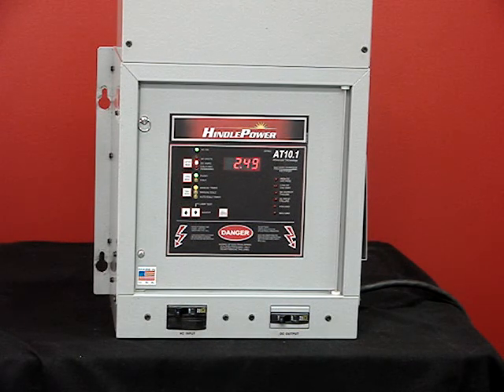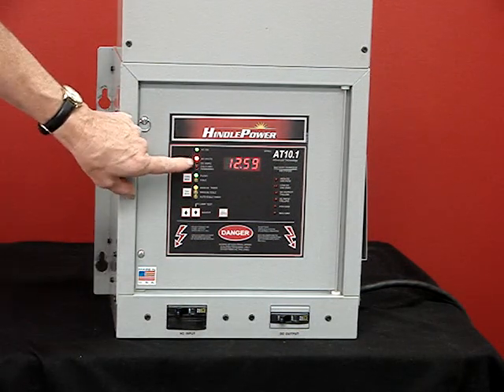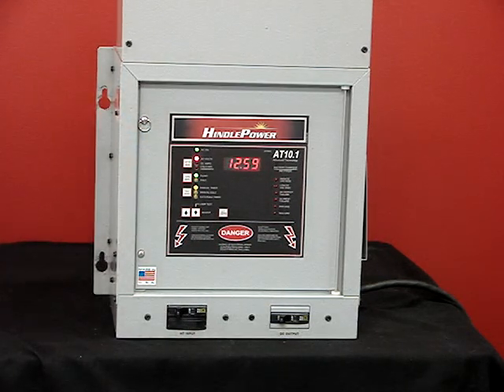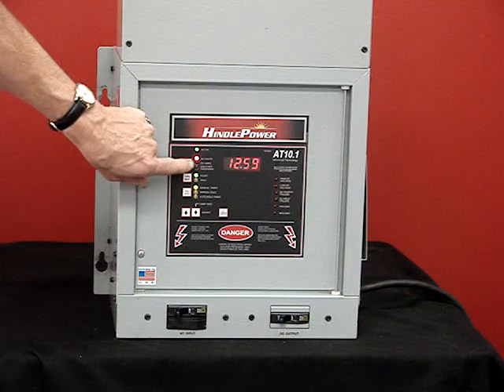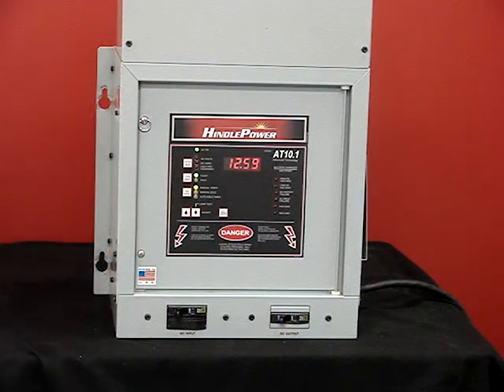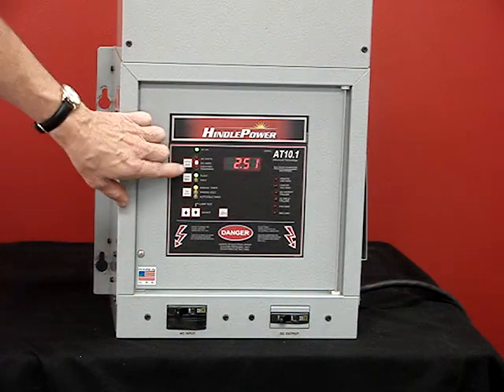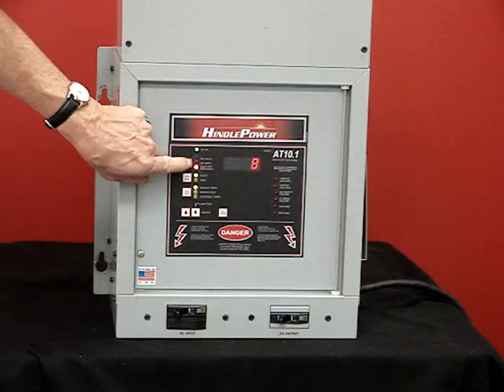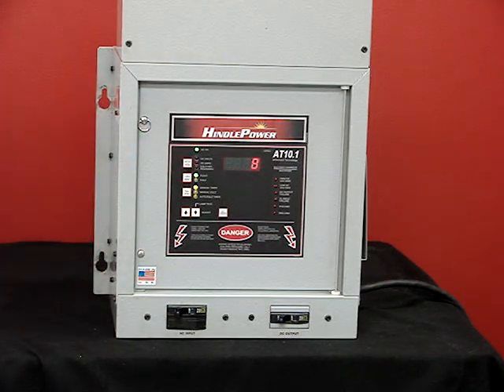This top button controls the meter output. By depressing it, it locks the meter on volts. The next press brings us to just showing amps. The last one shows the hours that need to run for the equalize timer. Depressing it one more time toggles back and forth from volts to amps.